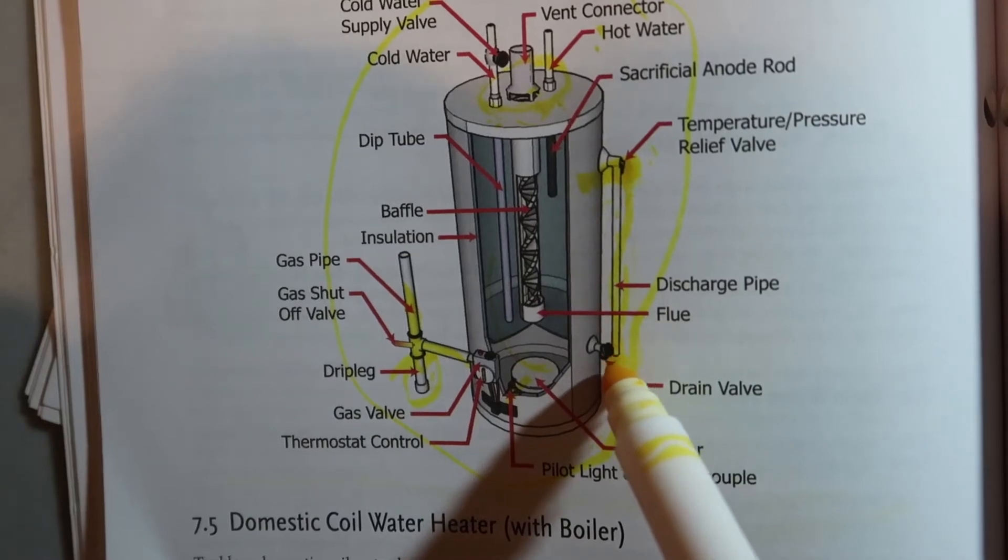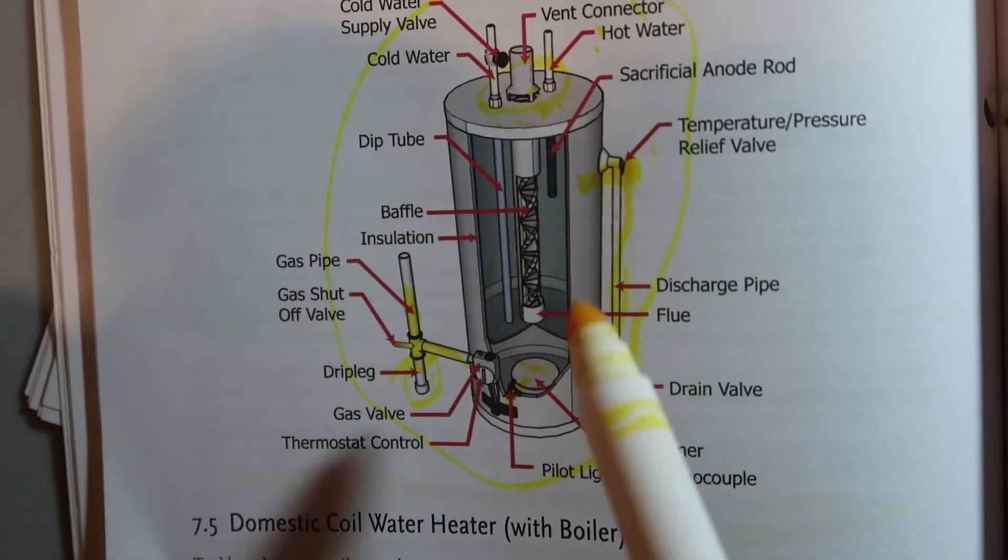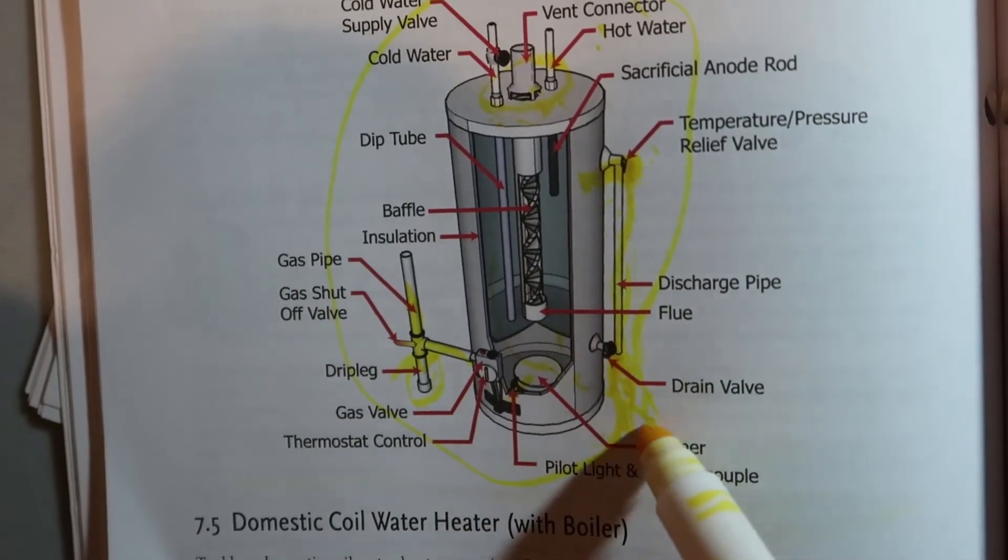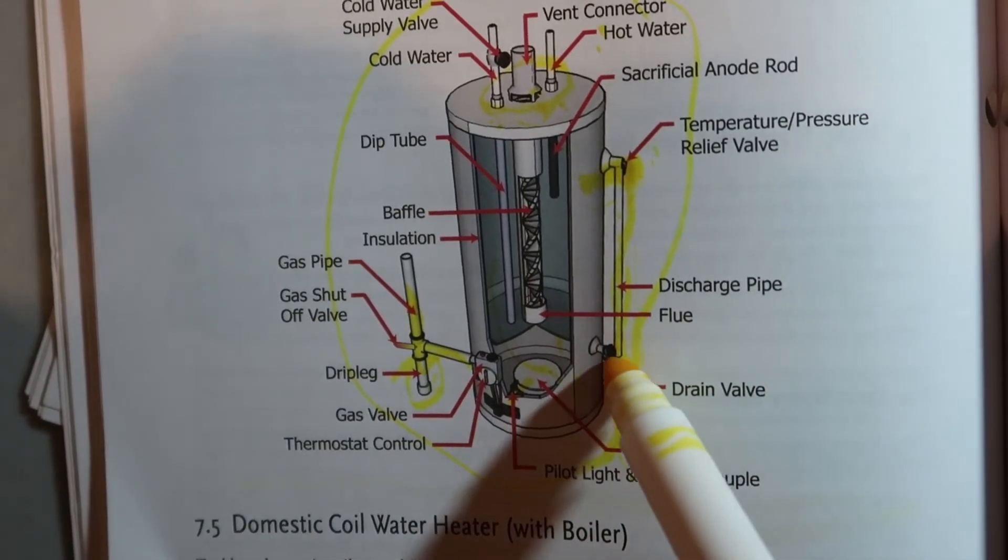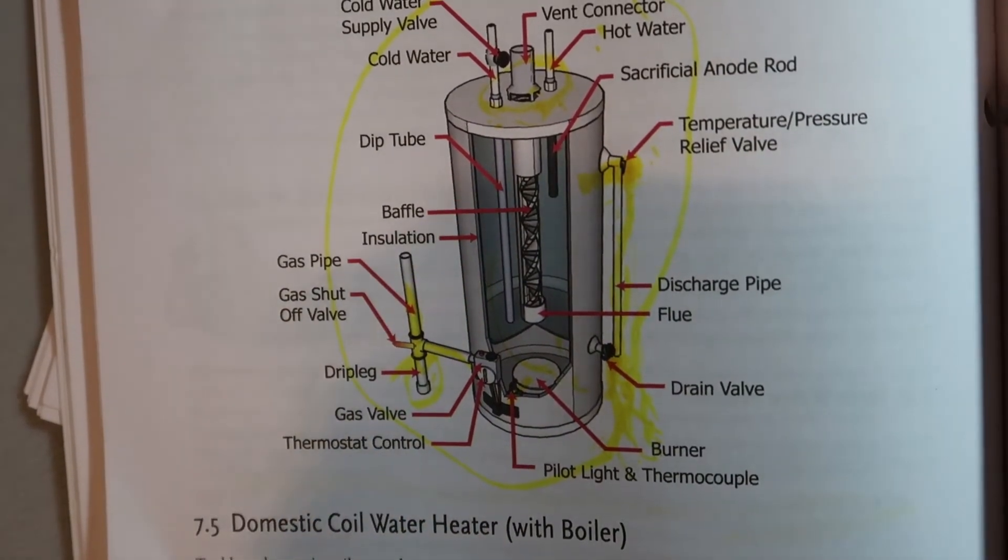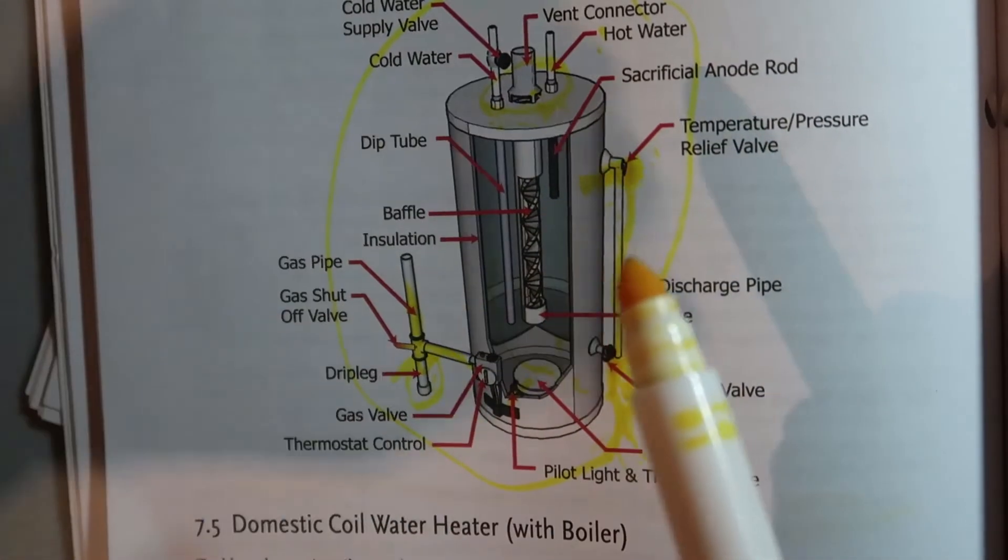You probably want to attach a hose to this and get you like a five gallon bucket and you want to drain it out each, let me rephrase that, just turn that on. When you first come out there's gonna be some sediment in the water until it goes clear. You're just draining out the sediment, shut it back down, and that will increase the life of your water heater.